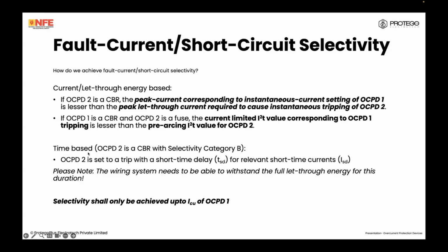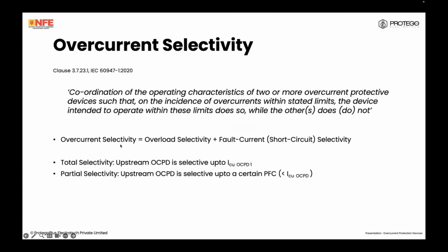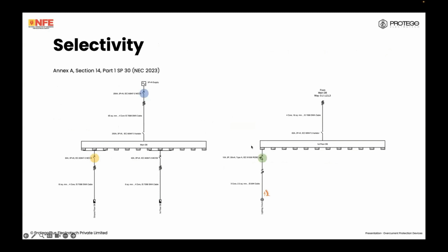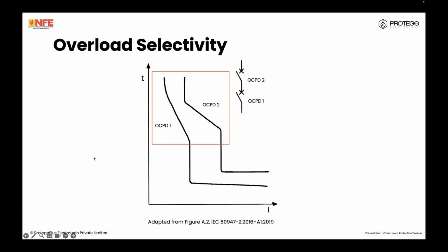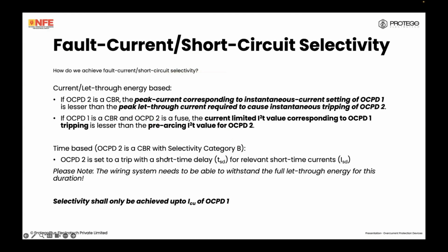Time-based selectivity also exists. So simply, you have a delay on this MCCB. It will wait for this RCB to clear the fault. If it doesn't clear the fault, then it will trip. So that's where you have the selectivity categories, and you have a defined ICW. The MCCB and the internal components can withstand that time of current. So simple: there's a short time delay, assigned for the relevant short time current, and it will wait. Very importantly, ICW is given by the manufacturer, but the whole wiring system needs to be able to withstand the full let-through energy for this duration. It could be even 0.05 seconds. This calculation needs to be done. I'll show you how to do it as well.